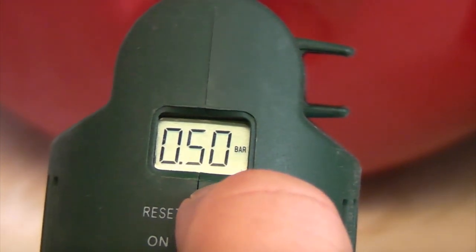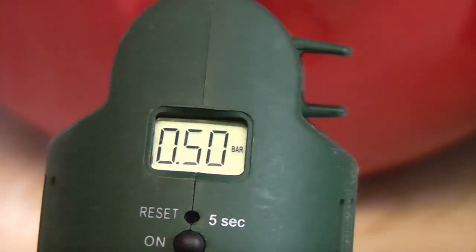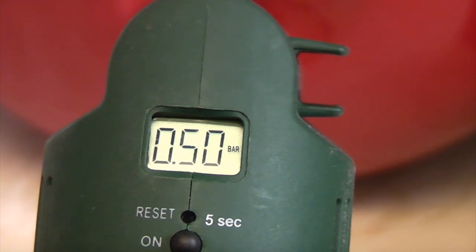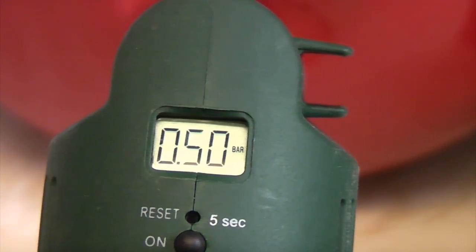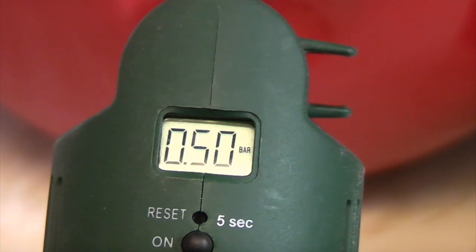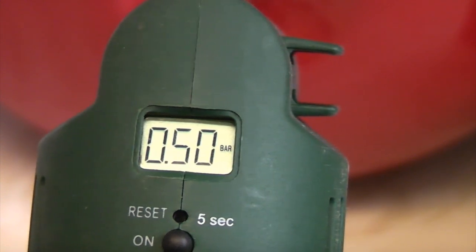You can see there that we've got half a bar of pressure. I've read the instruction manual for this particular boiler and it needs between 0.8 and 1.0 bar. So we do need to pressurize it a bit.